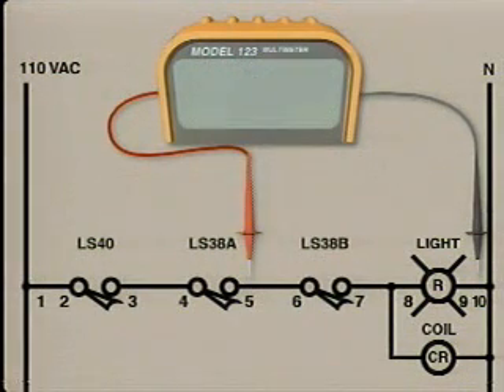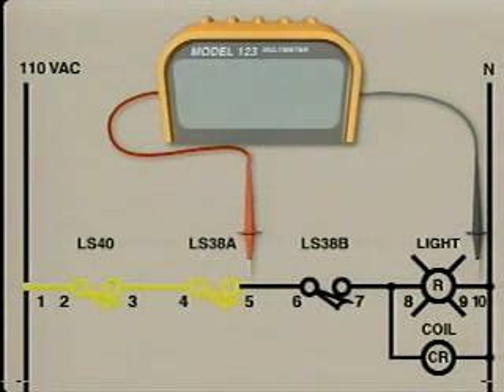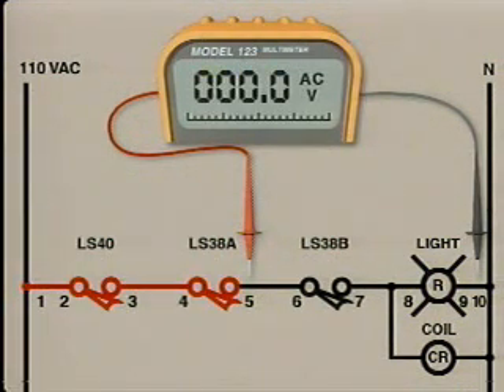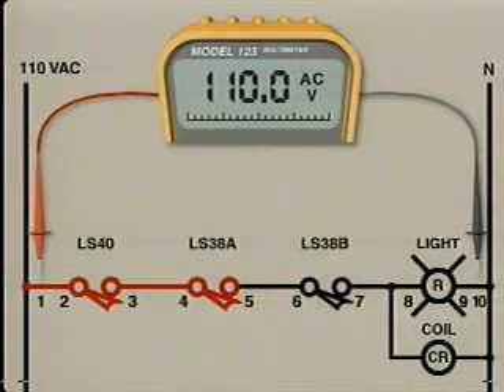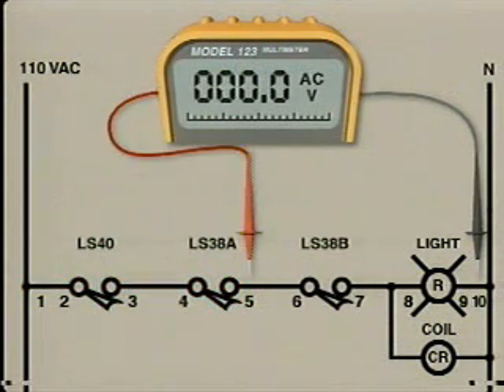Next, the electrician decides to half-split the circuit by testing for voltage at test point 5. The result of this test will indicate if the voltage at test point 1 is also present at test point 5. At test point 5, the electrician measures 0 volts. He verifies that the voltmeter is still operating properly by reading full line voltage at test point 1 again. A measurement of 0 volts at test point 5 means that the circuit's operating voltage, which is present at test point 1, is not reaching test point 5. This means that there is an open somewhere between these two test points.